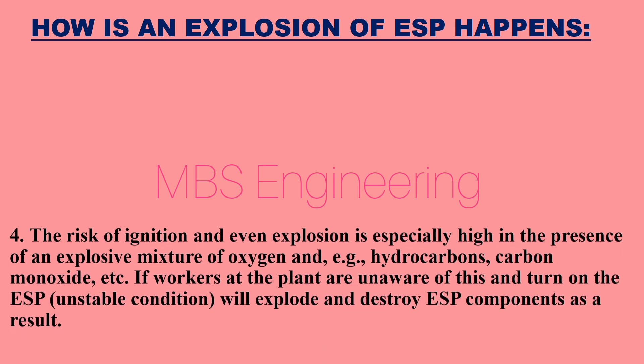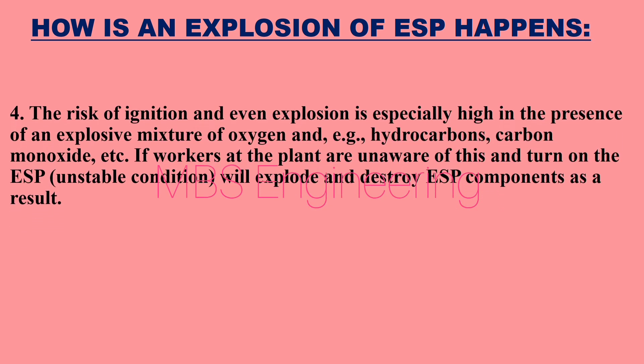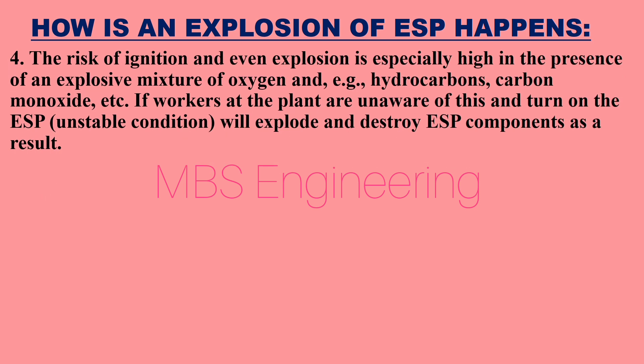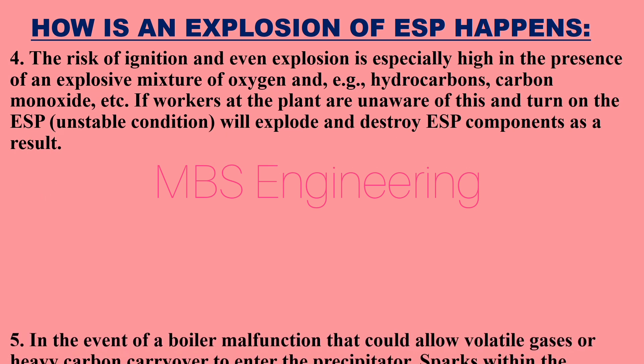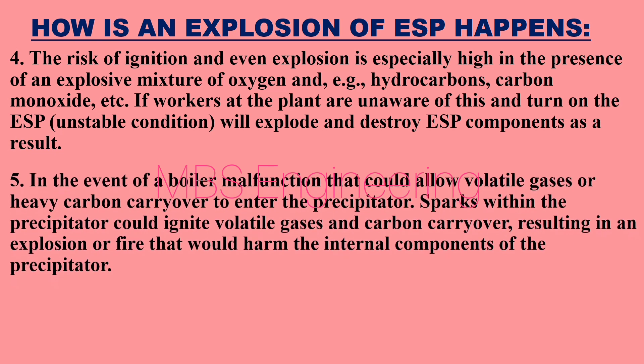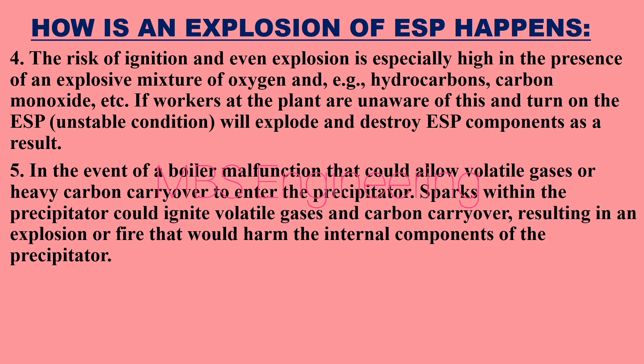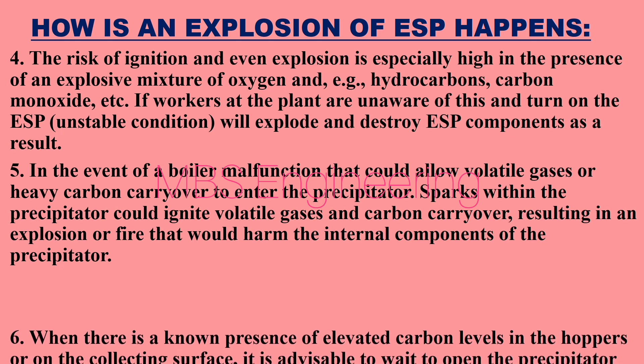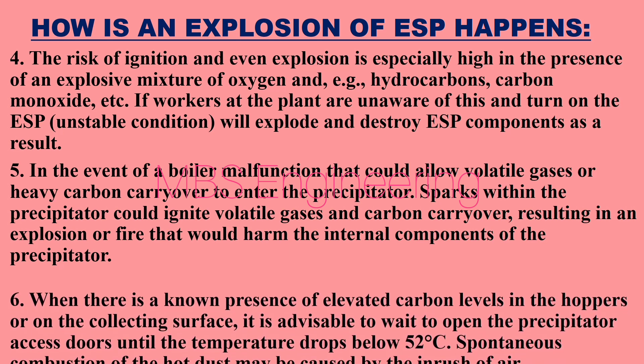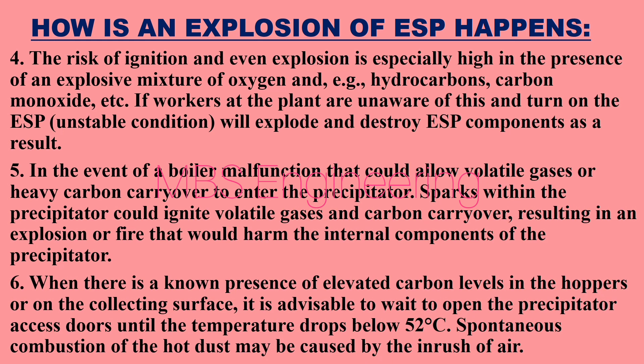Point 4: The risk of ignition and even explosion is especially high in the presence of an explosive mixture of oxygen, hydrocarbons, and carbon monoxide. If plant workers are unaware of this and turn on the ESP under unstable conditions, it will explode and destroy ESP components. Point 5: In the event of a boiler malfunction allowing volatile gases or heavy carbon carryover to enter the precipitator, sparks within the precipitator could ignite them, resulting in an explosion or fire that would harm the internal components.